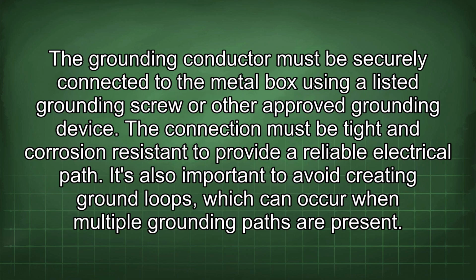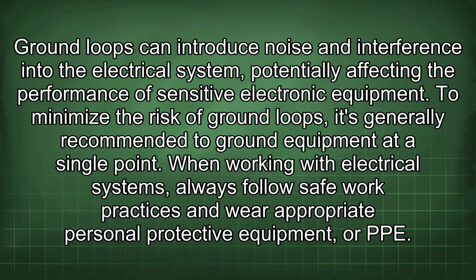The grounding conductor must be securely connected to the metal box using a listed grounding screw or other approved grounding device. The connection must be tight and corrosion resistant to provide a reliable electrical path. It's also important to avoid creating ground loops, which can occur when multiple grounding paths are present. Ground loops can introduce noise and interference into the electrical system, potentially affecting the performance of sensitive electronic equipment. To minimize the risk of ground loops, it's generally recommended to ground equipment at a single point.